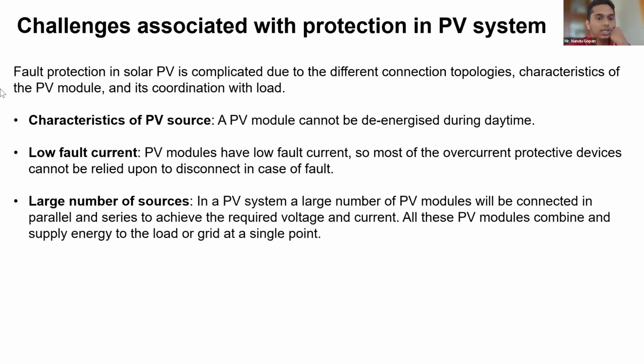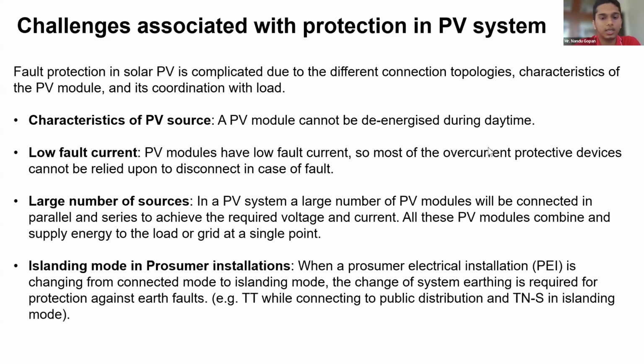And the next one is the large number of sources. Normally for a PV array, there will be a huge number of PV modules, and the problem is you can't give protection to each and every single PV module. You can only give it in a combiner box, or you can combine them and give protection, but that is also an issue. Next is islanding mode in prosumer installation. I'll be getting back to how islanding mode is affecting prosumer installation in the last few slides.